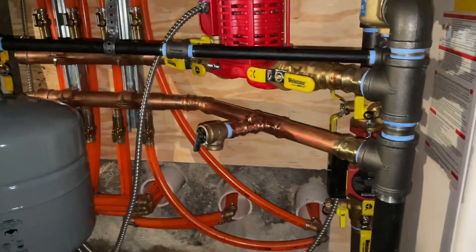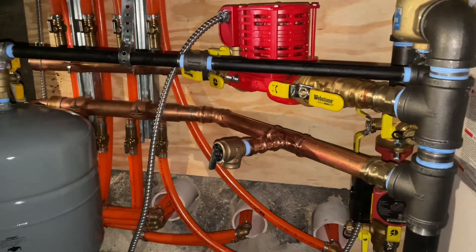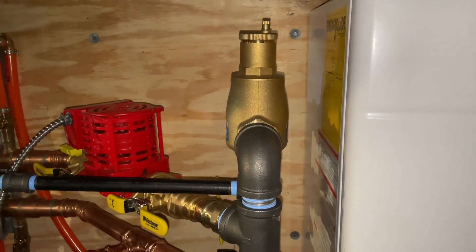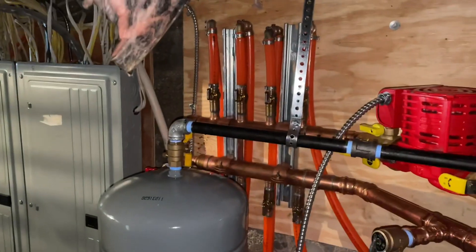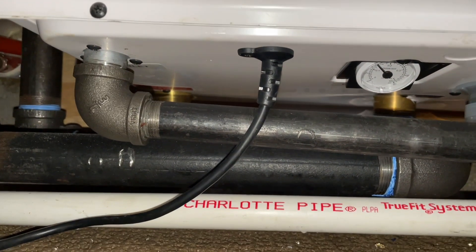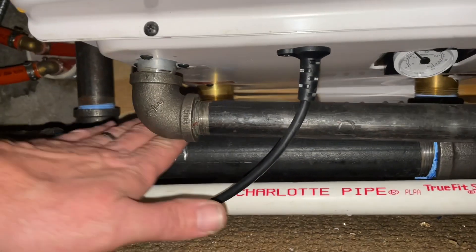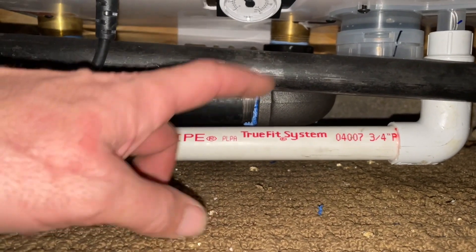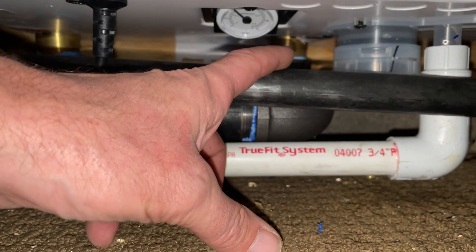He called me up panicking — 'St. Mike, you gotta hook me up' — so we got it done. I dedicated half a day here. I still have to finish the fresh air intake and support the expansion tank with band iron, but that's about it. Let's take a look at the Laars Mascot FT — this is a 199,000 BTU boiler only. I've never put in a Laars before, but this is what the engineer designed. This pipe right here is my return water coming from the system.